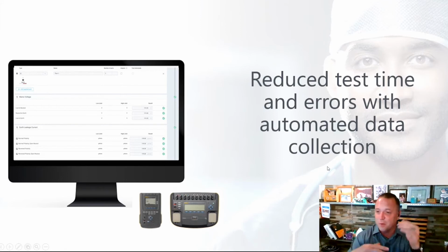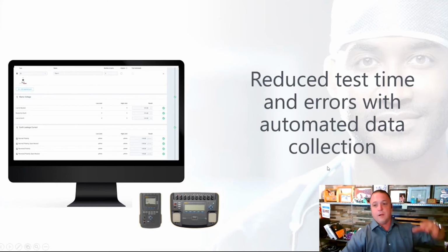But all that's run through, so you're not going through work orders saying, hey Jim, I was reviewing your work orders, you closed these all out, but do you realize on your defib you missed step 17 and don't have a result here? Now that technician has to stop what he's doing, get out the analyzer, get his PC, go out to the floor and find the device. And is it where you left it? If it's a defibrillator, maybe. IV pumps, nah, those things walked away. You've got to go find the device, set up everything, redo the test, fix that piece of data. That's a lot of wasted time—maybe an hour a day if you have to drive someplace.